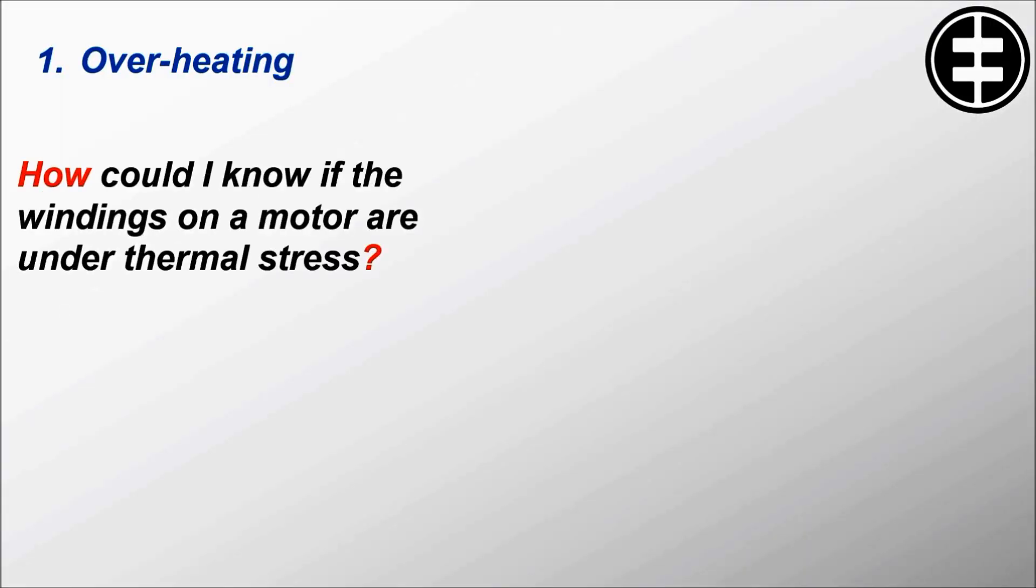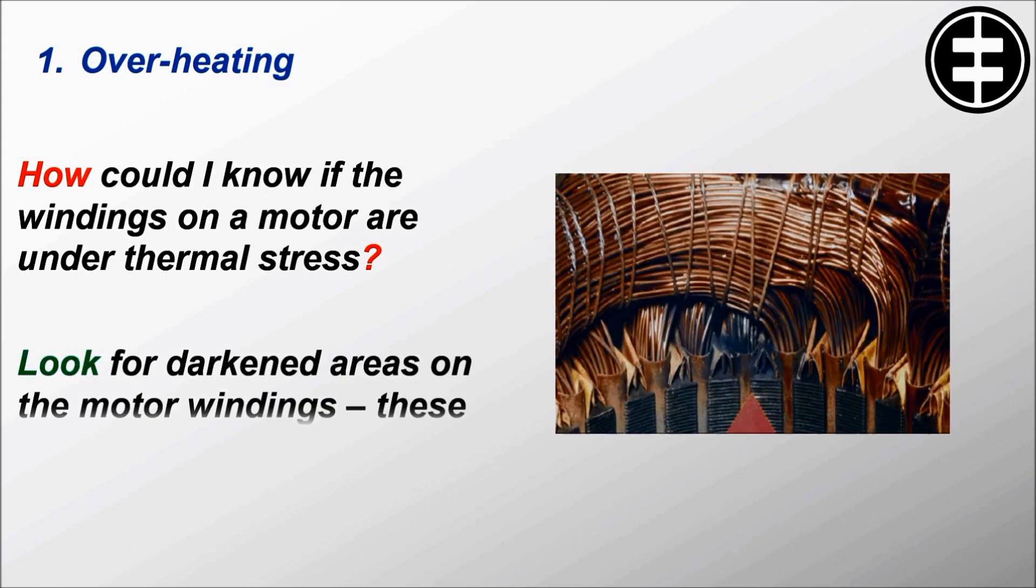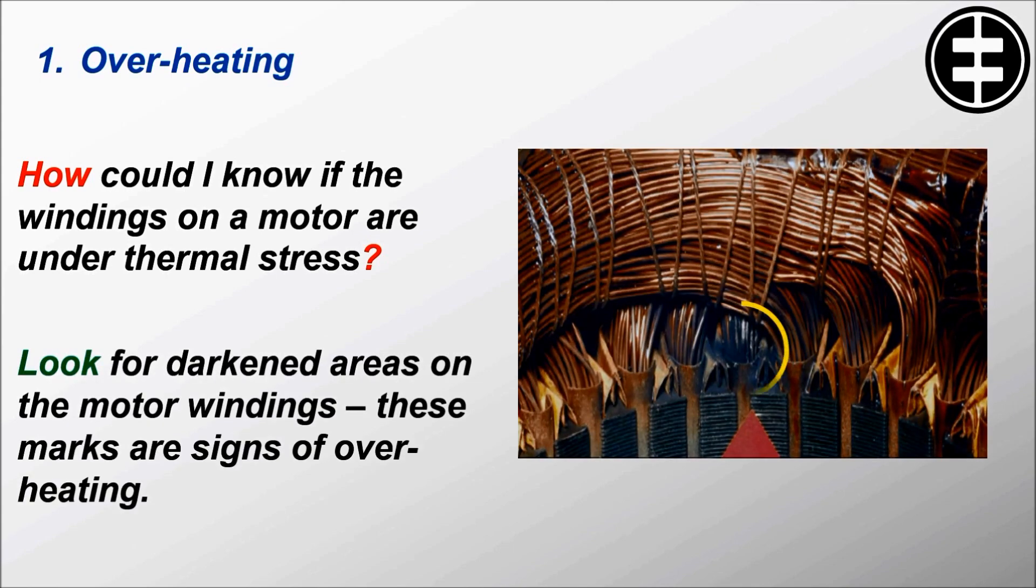How could I know if the windings on a motor are under thermal stress? Look for darkened areas on the motor windings; these marks are signs of overheating.